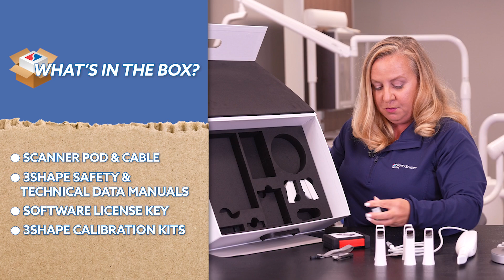This is your software license key. This comes with the actual box itself. You have your 3Shape calibration kits, and this has multiple pieces. So we'll get those all out too. So first here I want to highlight, this is the license or your dongle that is going to connect right into your laptop. This is your 3Shape Unite software. So this is going to be the version that comes in the box. I would suggest that when they set up your installation that they do update and download the latest version of the 3Shape Unite software. We don't want to lose it or misplace it. It stays in your laptop at all times and is never removed.